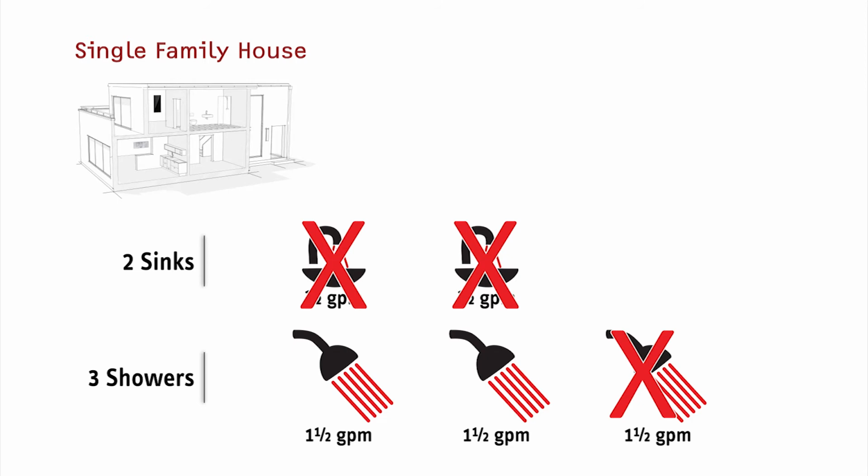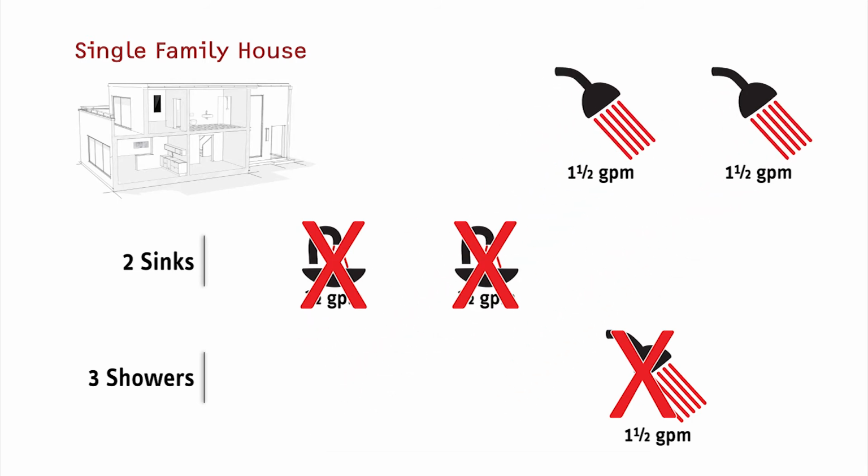Next, add up the flow rates from taps that must run at the same time. This doesn't mean to add up the flow rate for every hot water tap in the house. Most households don't need to run hot water from every tap at the same time. The easy way to do this is to add up how many showers are taken at the same time.